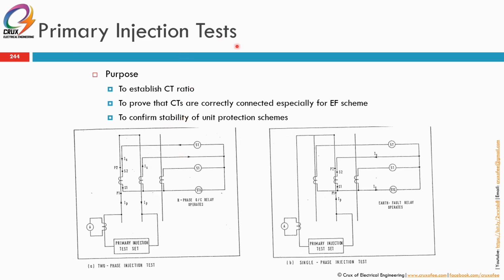So primary injection test, the purpose is to establish the CT ratio. Second is to prove that the CTs are correctly connected, especially for an earth fault scheme that is using summation or residual type connection. And also to confirm the stability of the unit protection scheme. So we will use primary injection test.